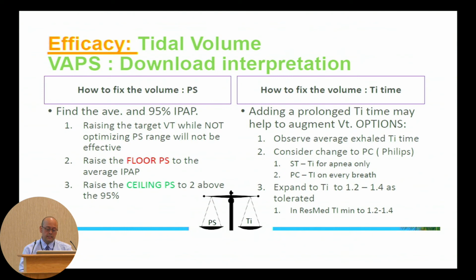In ResMed, typically they have a range of inspiratory times, so they give you TI min and TI max. So you definitely want to do your TI min 1.2. In Respironics, there is only going to be a TI, so it's going to be 1.2. If this is not enough, this is when you need to adjust your backup rate in order to achieve your target tidal volume or alveolar volume.